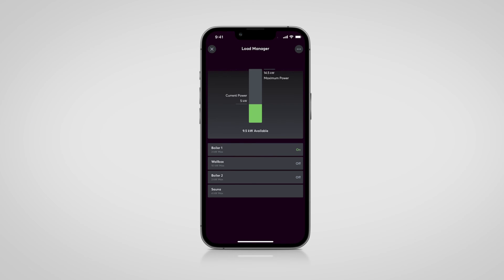The Load Manager monitors the current load in a building. In the event of a possible overload of the power, consumers are successively disconnected. With the Loxone Config 13.1, the Load Manager gets an update which also makes it perfect for commercial projects. In the commercial sector, the network operator determines the usage fee to be charged based on a maximum average power consumption over a fixed interval of 15 minutes. This parameter has now been added to the block, so that this 15-minute interval can now be taken into account.